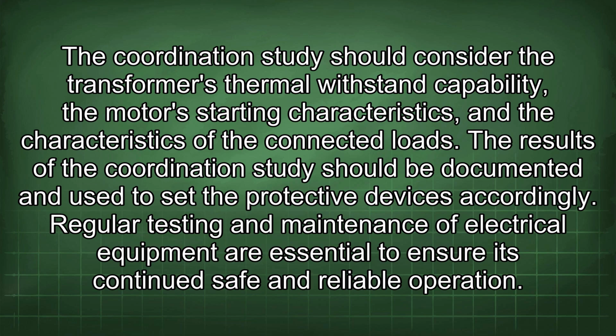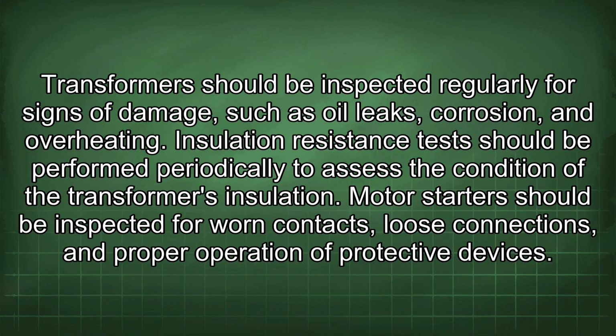Regular testing and maintenance of electrical equipment are essential to ensure its continued safe and reliable operation. Transformers should be inspected regularly for signs of damage such as oil leaks, corrosion, and overheating. Insulation resistance tests should be performed periodically to assess the condition of the transformer's insulation. Motor starters should be inspected for worn contacts, loose connections, and proper operation of protective devices.